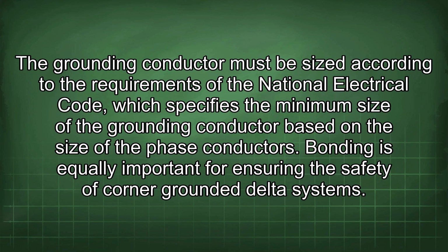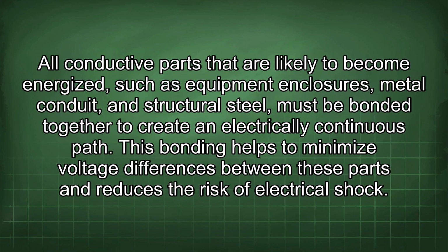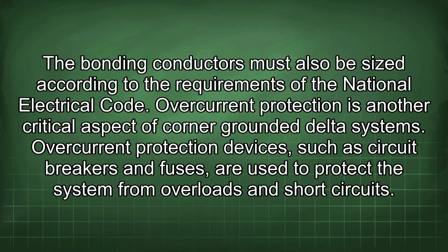Bonding is equally important for ensuring the safety of corner-grounded delta systems. All conductive parts that are likely to become energized, such as equipment enclosures, metal conduit, and structural steel, must be bonded together to create an electrically continuous path. This bonding helps to minimize voltage differences between these parts and reduces the risk of electrical shock. The bonding conductors must also be sized according to the requirements of the National Electrical Code.